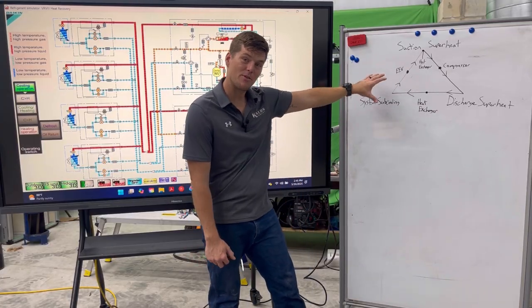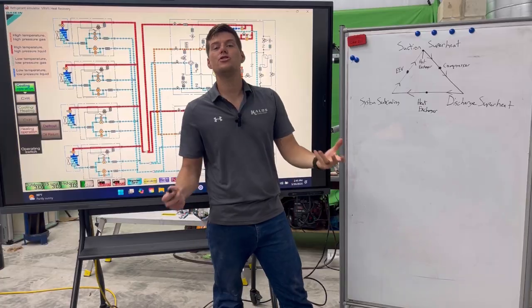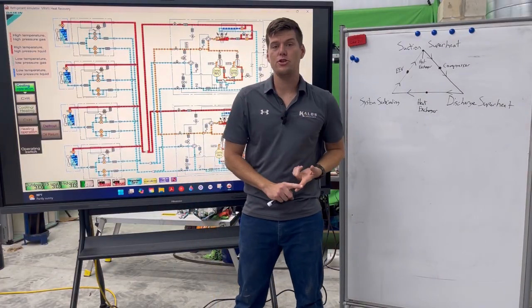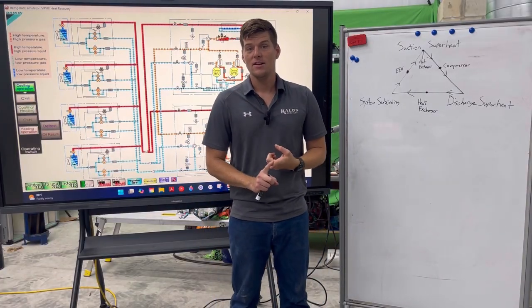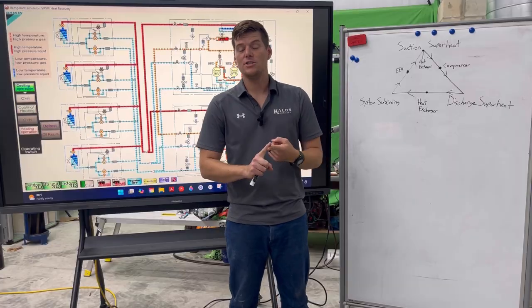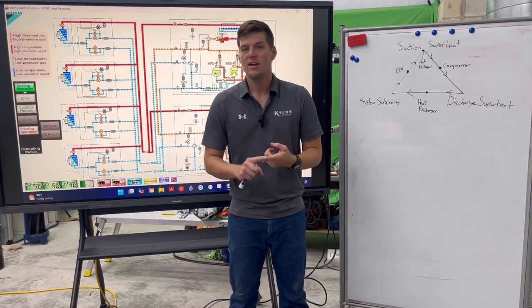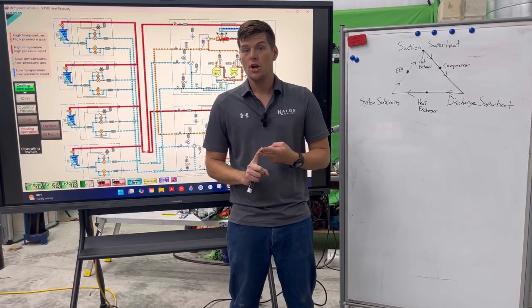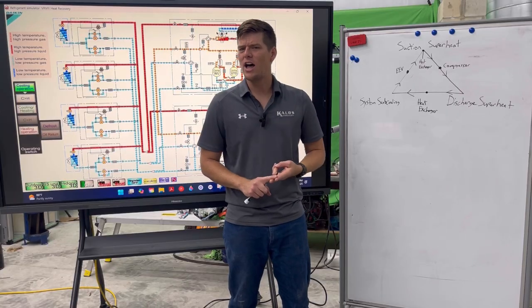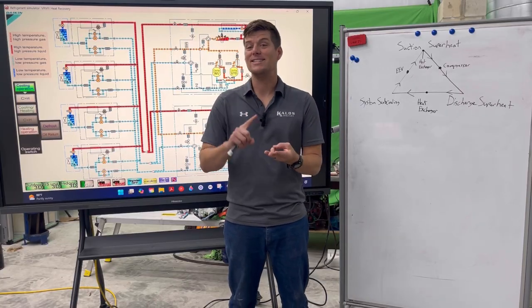This is more in depth than what I showed you last time. Last time I showed you numbers, we talked about if your discharge superheat is this, right, 70. Okay, well, that's not crazy high. It's still within range, but it is fairly high. And my suction superheat is 30, which is somewhat in range, but also on the high end as well. And my system subcooling is 0.